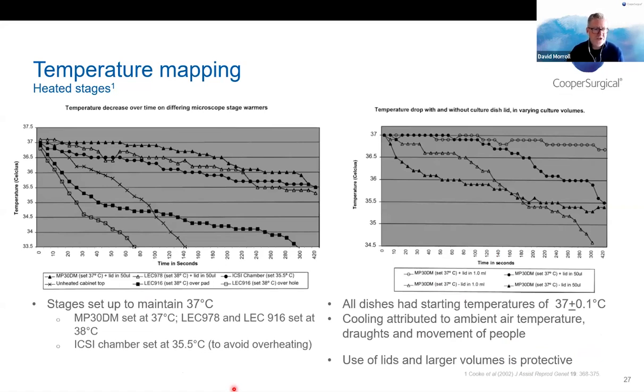Probably more of an issue are the heated stages. So this is taken from a study from quite a long time ago, 2002, by Cooke and colleagues. And what they did here is they looked at temperatures over time on heated stages. So they had a couple of different setups along with an ICSI chamber. So this is the polystyrene chamber that sits around an ICSI microscope. Now they deliberately set that at 35.5 degrees to avoid overheating, which if you read the paper is quite interesting because they clearly had a problem with the piece of equipment and yeah, probably not the best starting point.